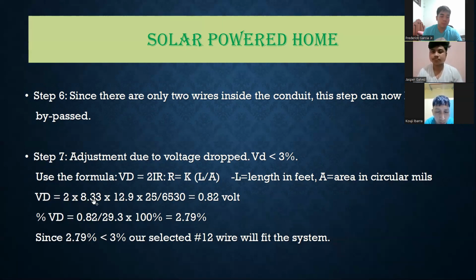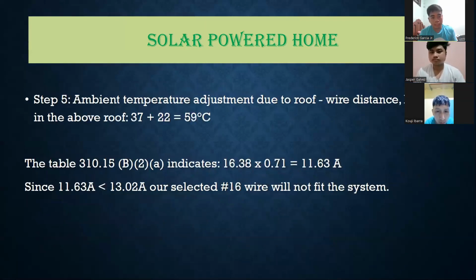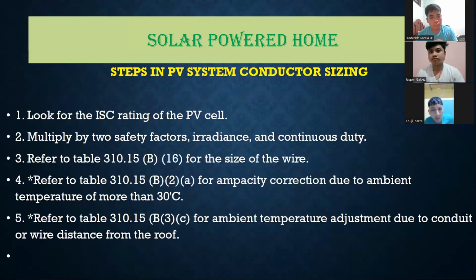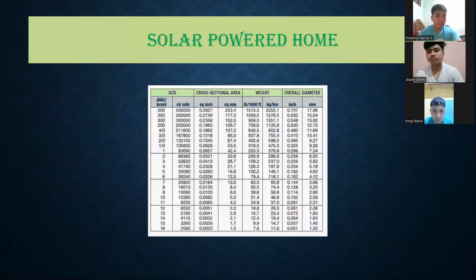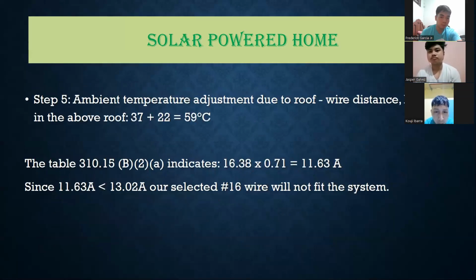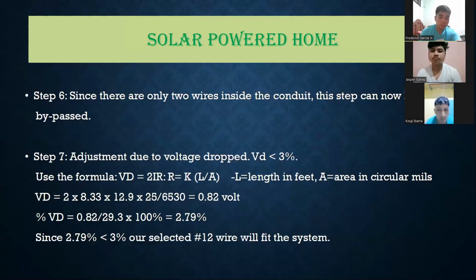The Isc, the current of the photovoltaic cell, times 12.9 K, times 25 over 6530. Now 25 we will assume is the length that we'll be using, and 6530 is the area in circular mils. We can see the area in circular mils from this previous table right here. Since we have a number 12 AWG, in circular mils that is 6530. So we just plug in that value into the equation, and we're left with 0.82 volts.